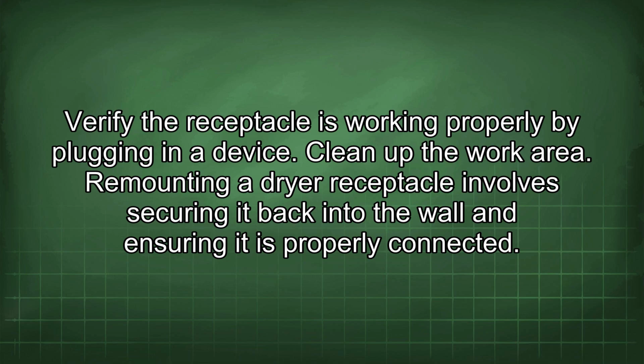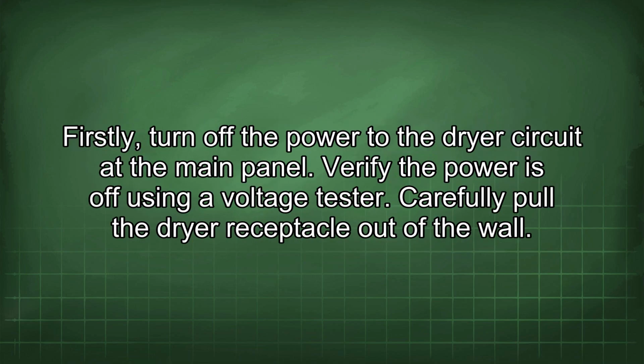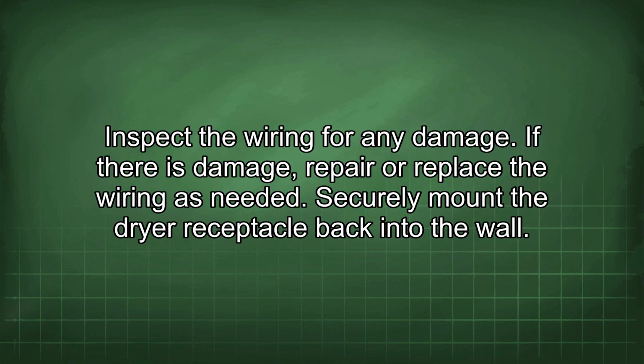Remounting a dryer receptacle involves securing it back into the wall and ensuring it is properly connected. Firstly, turn off the power to the dryer circuit at the main panel. Verify the power is off using a voltage tester. Carefully pull the dryer receptacle out of the wall. Inspect the wiring for any damage. If there is damage, repair or replace the wiring as needed.